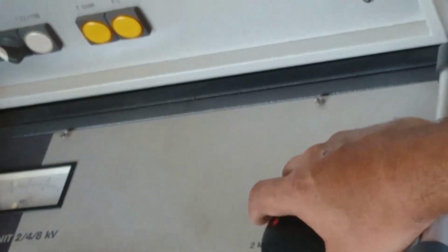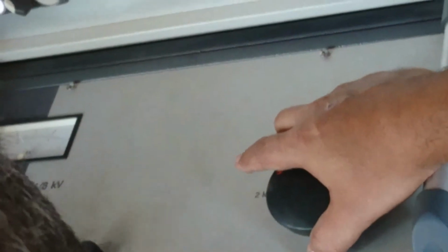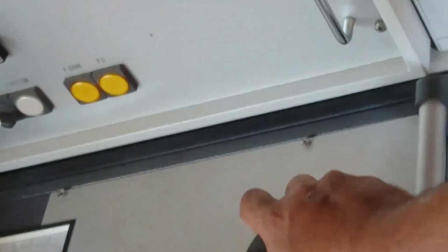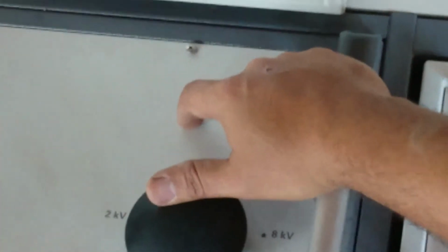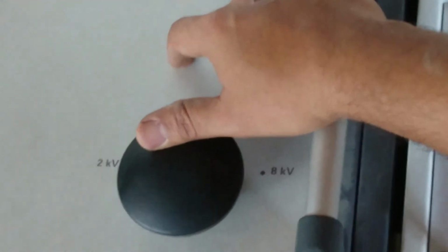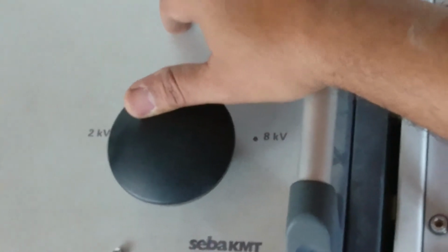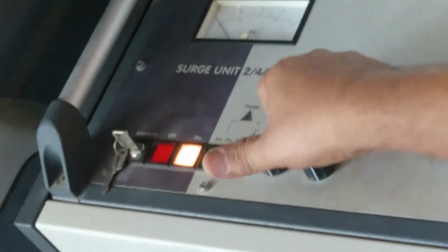I can also change it, just for here. Maybe we need more voltage because of the gap. I'll just make it on 4. But on field, don't exceed 2.5 kV on these types of cables. So that's why I go to 4, I can go up to 2.5 kV. Start, HV on, timer on 0.